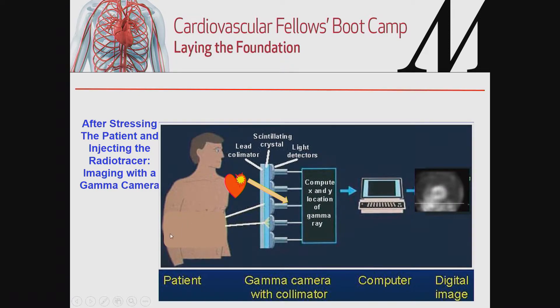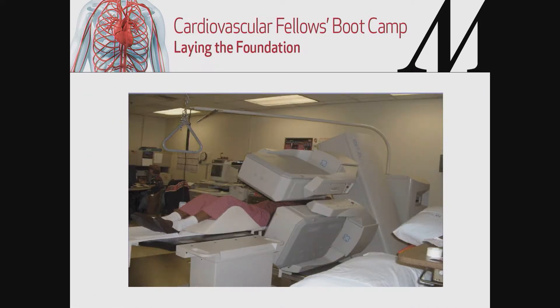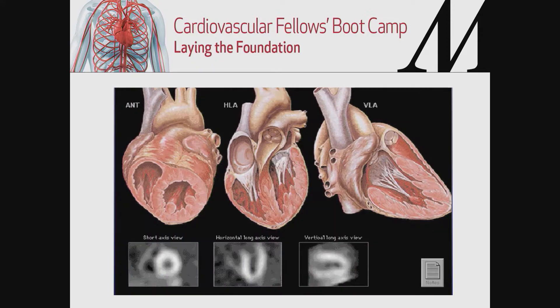After injecting the patient with a radiotracer and subjecting them to a stress modality — exercise or vasodilators — the nuclear camera, composed of a sodium iodide crystal and a lead collimator, collects the photons emitted from radioactive decay of the injected tracer. All those counts are digitized to produce a digital image. Most cameras have two heads and rotate around the patient in a 180-degree arc to collect all emitted photons.